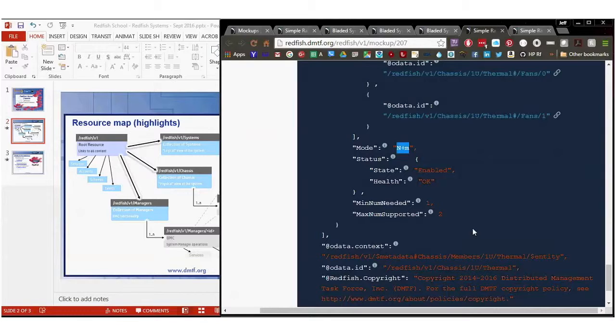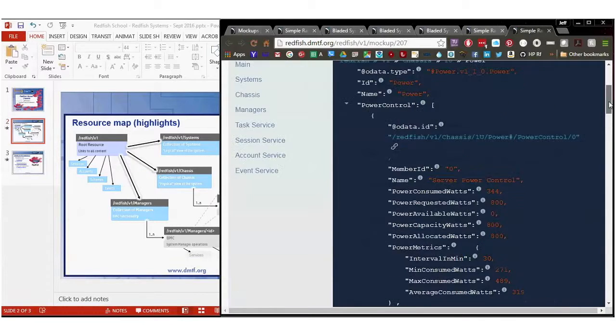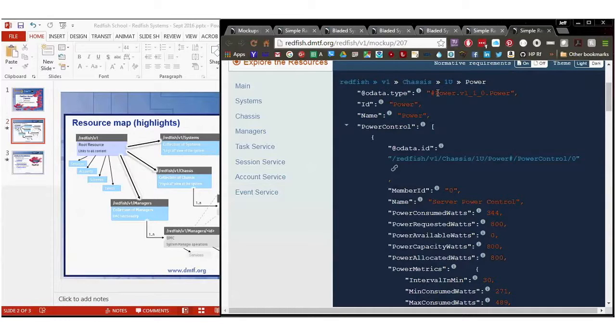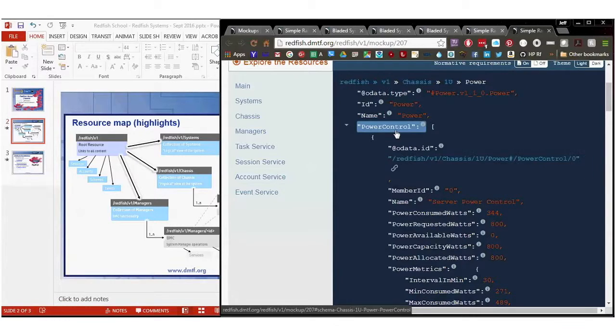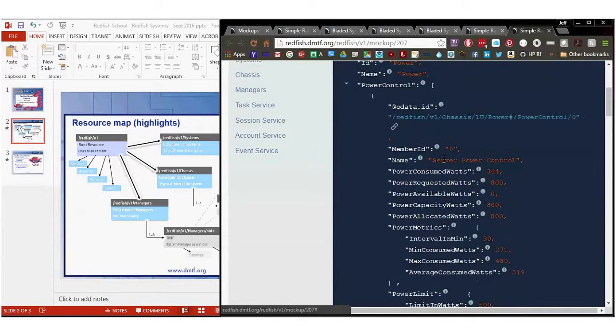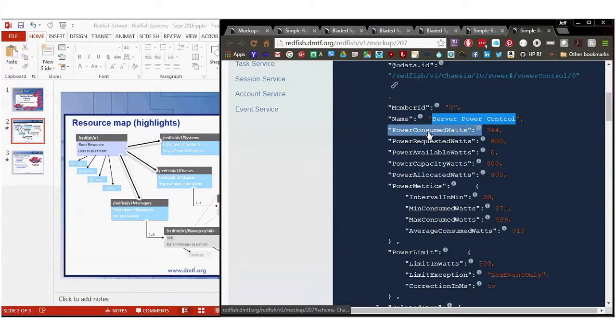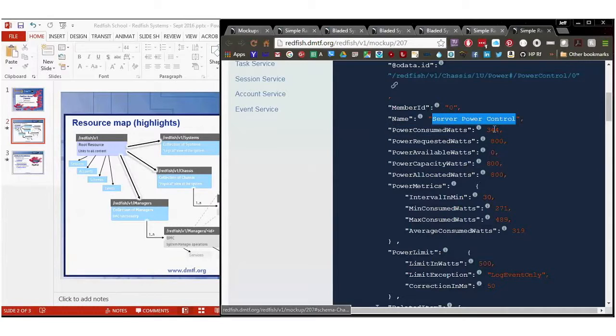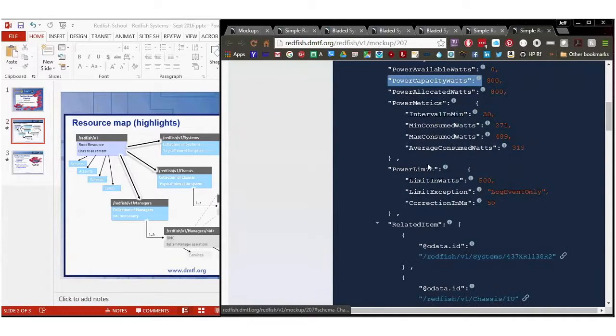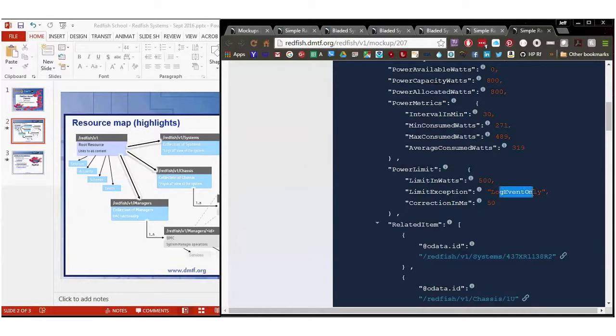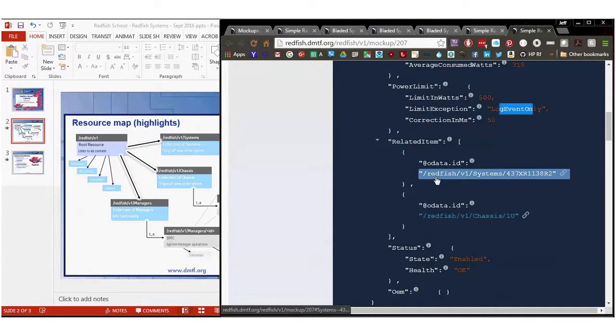Looking at power, here we have an object power. This was off of the system. Just like every other array, this has an OData ID. This is power control zero. What is it? It's the server power control. My metrics consumed in watts, available watts is zero. Capacity is 800. I'm only at 344 right now. This one is power limited, so it's power limited to 500. And the exception is really just tells it to log the event. It's related to this particular system. That's its power cap. And the status of this power cap is okay.